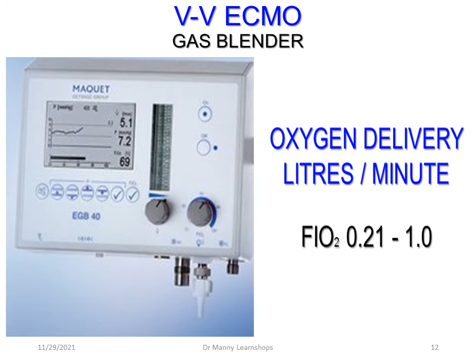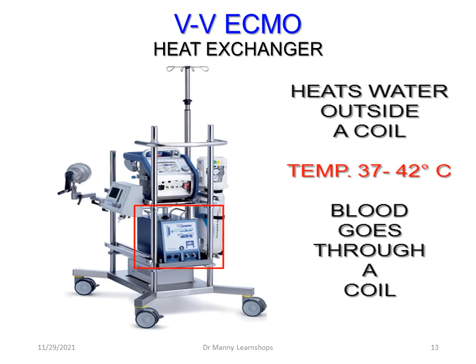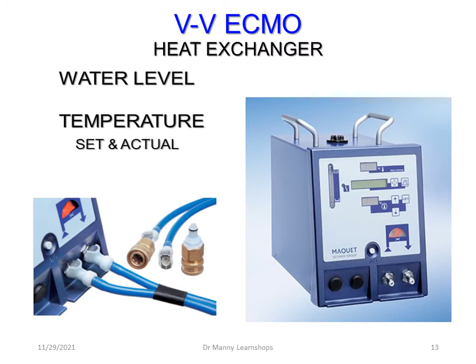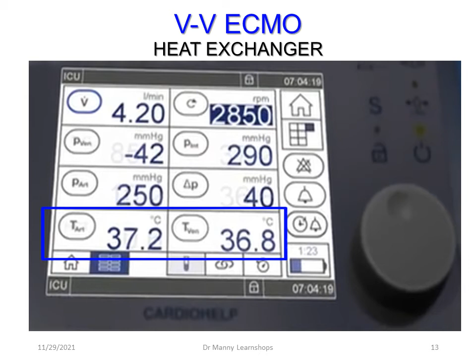When you look at the heat exchanger, this heats water outside a coil, and the temperature range is typically 37 to 42 degrees centigrade. Blood goes through a coil and is heated. You can have two water levels which are set, the set temperature and the actual temperature. So you can set the temperature and you can measure what the actual temperature is in the V-V ECMO heat exchanger Maquet system. It also measures the arterial and the venous. Now remember, there is no arterial. So it's the access and the return temperatures of the blood. It's measuring how warm the blood is coming out, and it's measuring how warm the blood will be sent back to the patient.